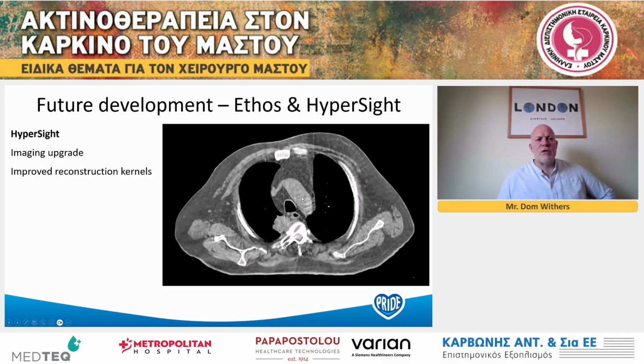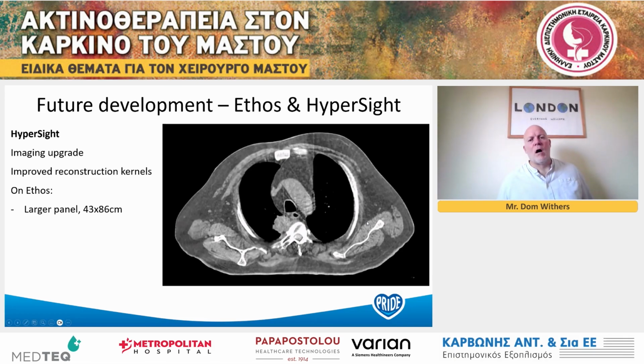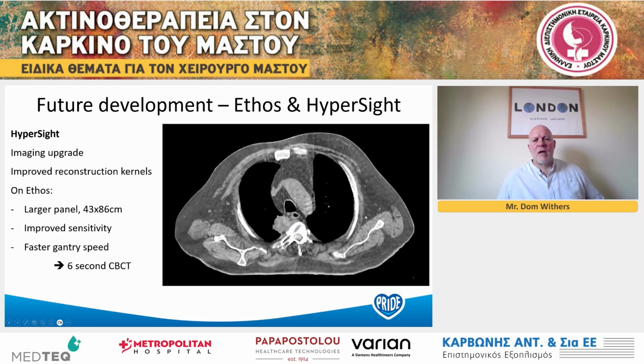So it's an imaging upgrade. There are improved reconstruction kernels that limit artifacts from breathing and also metal as well. And on Ethos, it's a much larger panel. It's twice the size of the usual panel on a conventional machine, which means that you only have to half arc instead of a full arc with an offset panel. There's also improved sensitivity on the panel. And with the faster gantry speed, it means you can have a 6-second cone beam. So it's definitely possible to do very good quality cone beams in breath hold for 6 seconds.